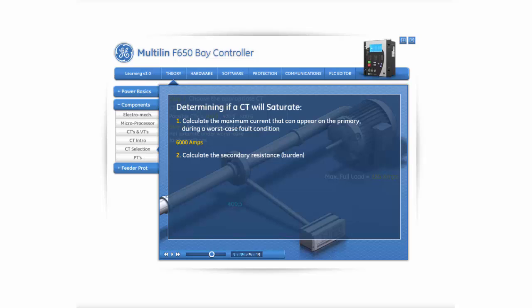The phase CT's secondary resistance, that is, the resistance of the windings on the CT, is equal to 0.088 ohms. The length of each wire from the CT to the relay is 50 meters and has a rated resistance of 2.5 ohms per kilometer. The total burden is equal to the CT secondary resistance, which is 0.088, plus 2 times the lead length of 50 meters, multiplied by the lead resistance of 2.5 ohms per kilometer, and then divided by 1,000 meters. This is then added to the relay burden of 0.008 ohms, resulting in a total burden of 0.346 ohms.